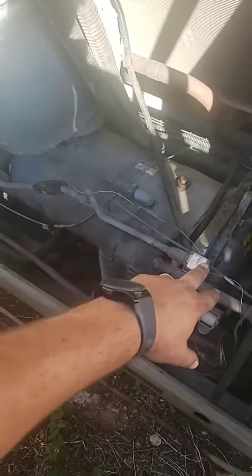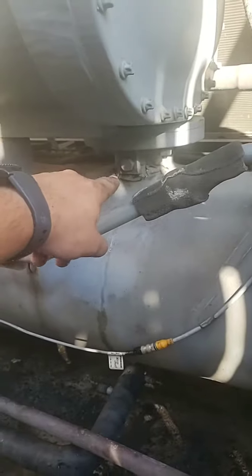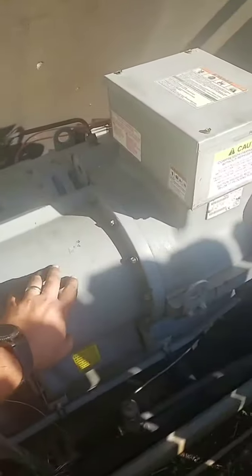So, like I was saying, this barrel here is our evaporator. The suction port on our compressor is right down here. So this is your suction getting pulled in. Comes up into the compressor, up in this cavity. This is where your screws are. Alright? So, just real quick on the screws themselves. Screws are a bit of a different animal. These are right at 70 tons in size each.